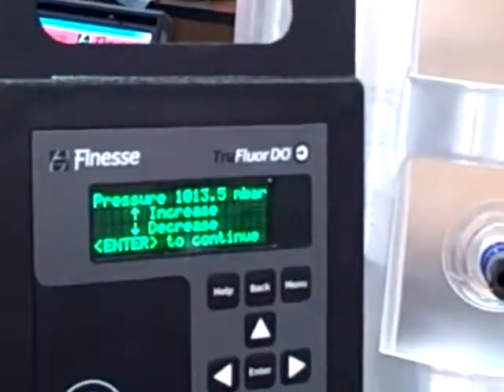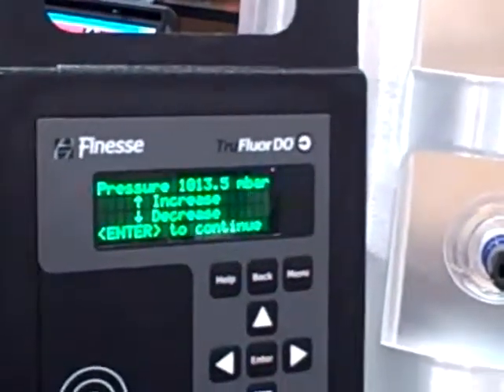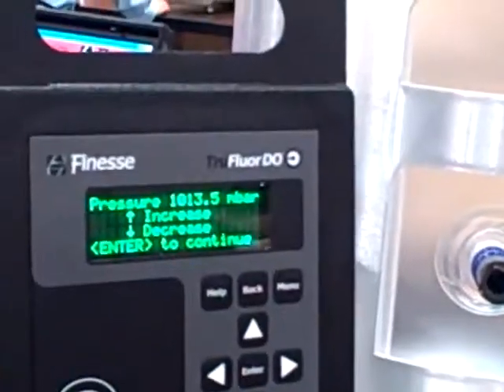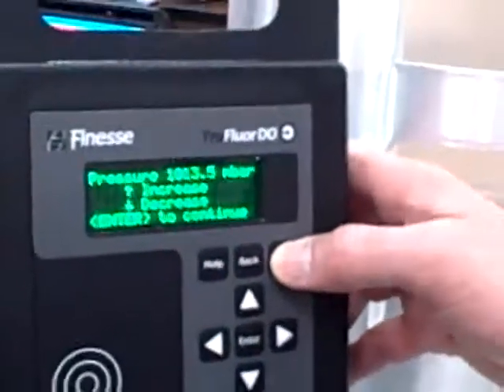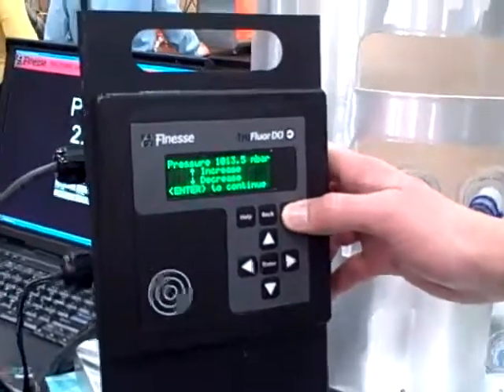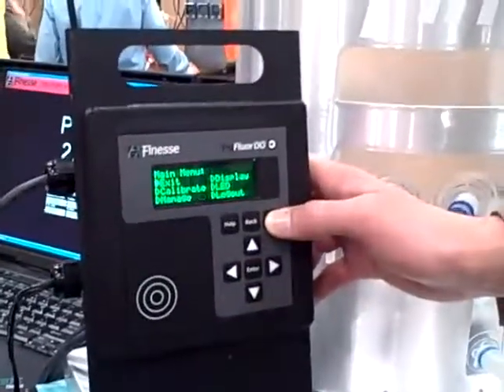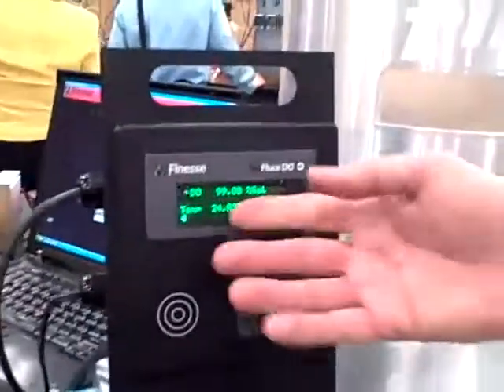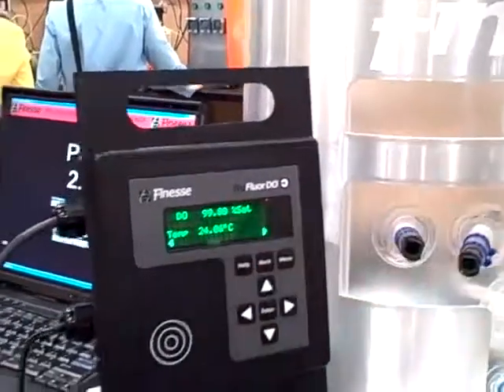Press enter, and you can do a pressure compensation for altitude. If you're in Colorado at high altitude, you need to do an altitude correction. So that's what this is for. In this case, we're near sea level, so we're just going to leave it where it is. Press enter twice, and it's already reading the DO and the temperature.